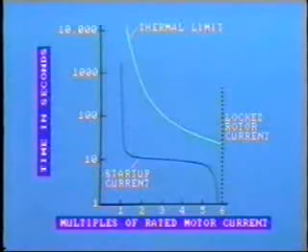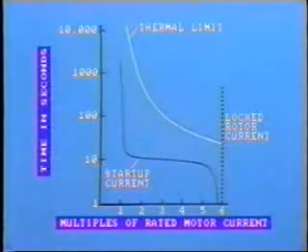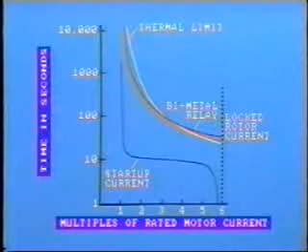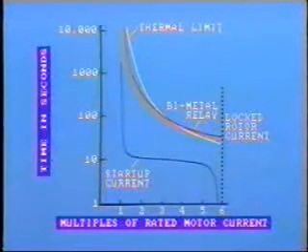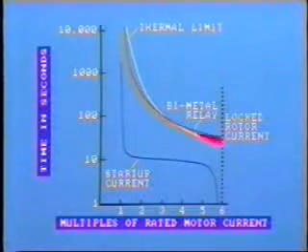So the thermal relay curve has to be set within this area here, between the thermal limit curve and the startup curve. In practice, we try to adjust the relay so that its tripping curve is quite close to the heating curve, like this, so as to prevent inadvertent tripping. However, it is quite impossible to get the curves to match exactly, and we will probably find that for high values of current, the bimetallic switch is too slow.